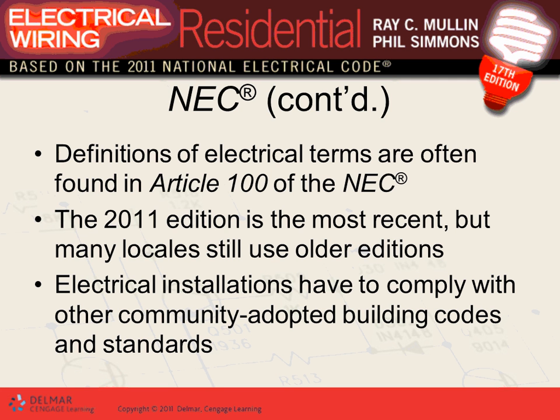2011 is the copy that we use. Also, communities adopt building codes. There are building codes and standards, guys, as designers, that you have to be aware of. For example, for energy codes, when you put outlets in an outside wall, they have to be energy code outlets. You couldn't put any box. The box has to be designed not to allow air to come from the outside to the inside. That's not an electrical code requirement, that's an energy code or building code requirement. Building code requirement also means, as you put switches in a public building, you must maintain the height of the switches between the minimum and maximum for disabled access.